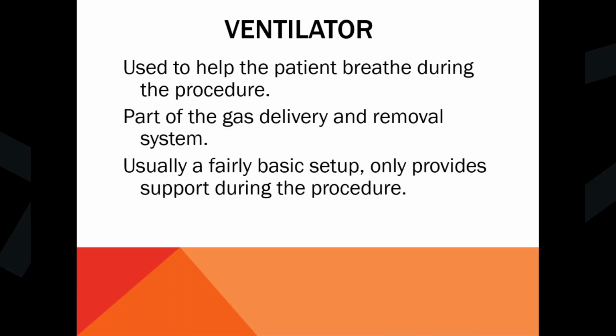The ventilator also is part of the gas delivery and removal system, so the same circuit that the ventilator is using to deliver air to the patient, that's also where the gas is delivered to the patient and then also pulled out with the exhalation. Most of your ventilators are fairly basic on the machines. It won't be like the type that you use for like therapy or like in the ICU. They used to be just a basic pressure ventilator. Now I think you have the ability to select between either volume or pressure or just volume ventilation. And basically it's just there to keep you going until they're done with the case and you're off the anesthesia.